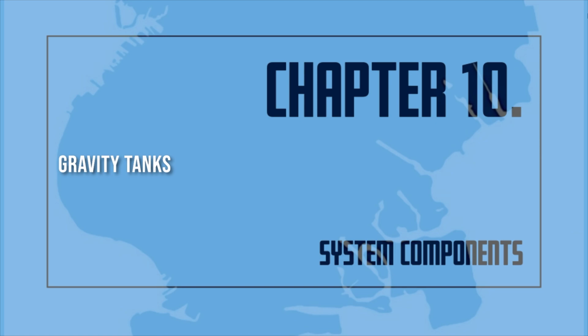All gravity tanks have an overflow pipe that drains off excess water in the tank. This happens if the floats do not turn off the fill pump. A fill pump is not necessary if the water pressure in the city water main is able to keep the tank filled with the correct amount of water. Gravity tanks are exposed to very low temperatures. All parts of the gravity tank must be insulated or heated to keep the water from freezing.